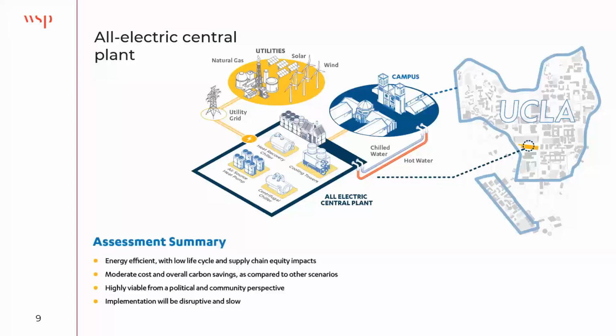The way that happens is to take the cogen plant offline, retain it for backup as we discussed, but install a large heat pump that's capable of producing steam. That heat pump would be run electrically, and it would essentially be plugged into the steam network and replace that part of the function of the cogen plant.